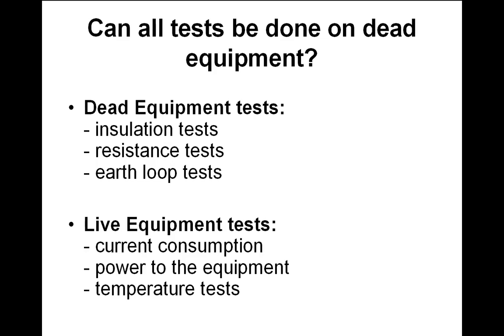Right, next one. Can all tests be done on dead equipment? This is a big question. And ideally, yes, if you can turn off the equipment and do some tests and take some measurements, it's good. You should do things like insulation tests, resistance tests, and earth loop tests. That would have to be done on dead equipment.